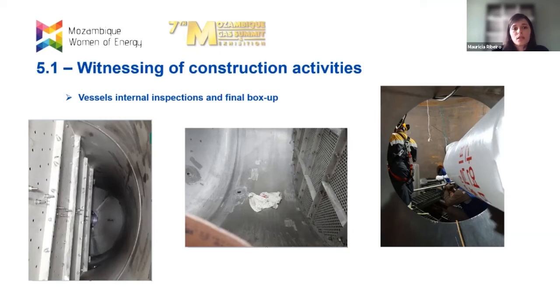One important thing when we do those vessel inspections, especially for confined space entry, is the permit work and isolation. We need to be sure that nobody will be able to put any kind of energy inside our system. It will be fully isolated, with no fluid connection or anything, so we need to be sure nobody can connect anything to our system prior to entering the vessels.